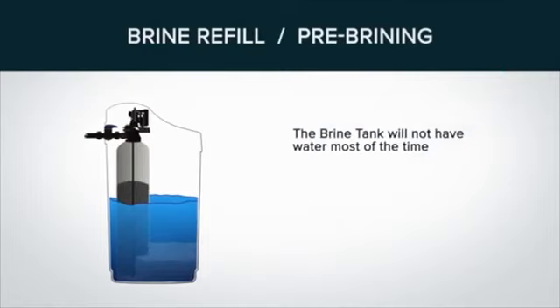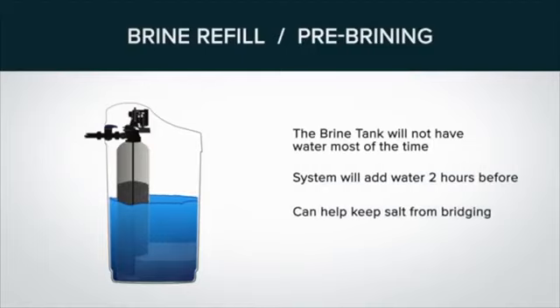When a regeneration is required, the system will add water to the brine tank about two hours before the process begins to allow the water to dissolve the salt into a brine solution. Pre-brining can help keep the salt in the brine tank from bridging, but will delay the regeneration process by two hours if you ever want to force an immediate regeneration.